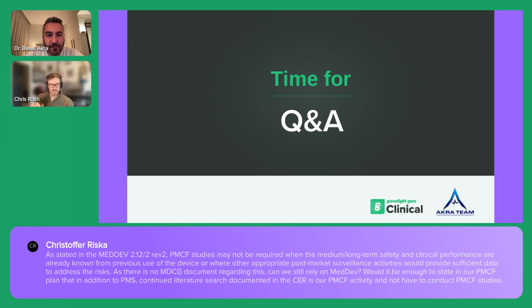So actually, as I mentioned before, a PMCF plan, contrary to the directive requirement, is actually an obligation for all manufacturers due to one factor: the general PMCF, which relies on literature. Literature cannot be avoided. You need to search the literature. But you can avoid a PMCF study in case you have sufficient data for your device.